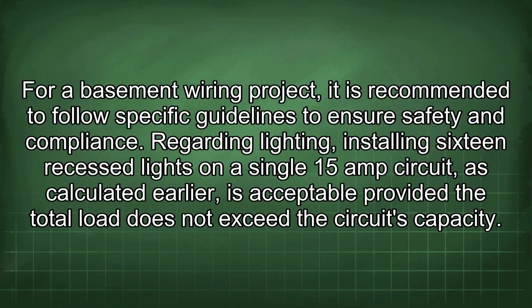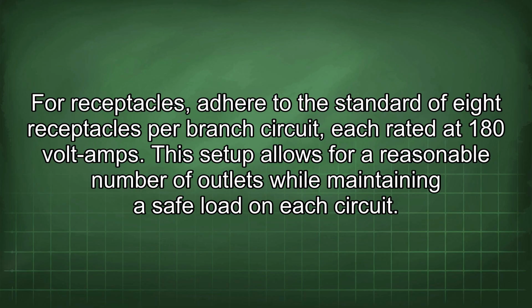Regarding lighting, installing 16 recessed lights on a single 15 amp circuit, as calculated earlier, is acceptable provided the total load does not exceed the circuit's capacity. For receptacles, adhere to the standard of 8 receptacles per branch circuit, each rated at 180 volt amps. This setup allows for a reasonable number of outlets while maintaining a safe load on each circuit.